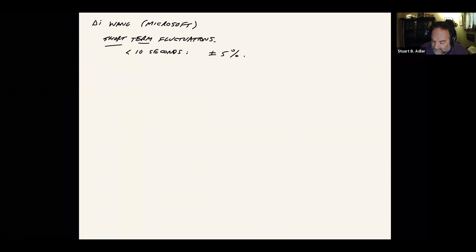And these short-term fluctuations, and by short term I mean less than 10 seconds, would be plus or minus 5% usually. So this just represents the kind of natural fluctuations you have in electronic componentry over time. And our system has to be able to handle that for sure. And it probably needs to be able to handle that without any kind of control. So you can't rely on the fuel cell to, 'Oh, you need a little bit more power. Now I will ramp up and produce more power. And no, you need a little bit less power. I will ramp down.' That's fine if you're talking about half an hour timescale or an hour timescale, but if it's less than 10 seconds, usually a fuel cell can't respond that quickly. And we'll talk about some of the reasons why that is. So we have to design our thing with some robustness here. It has to be able to handle these loads in a sort of passive way at plus or minus 5%. And we'll talk about some of the implications of that.